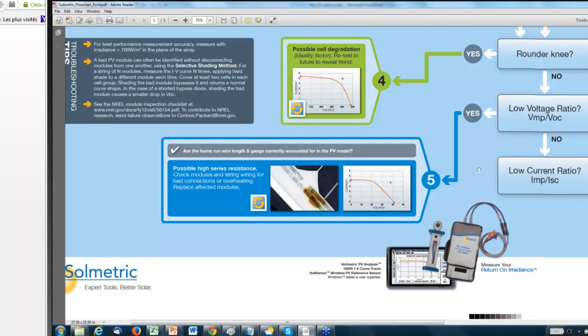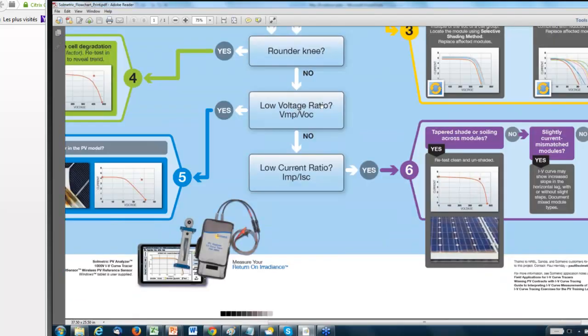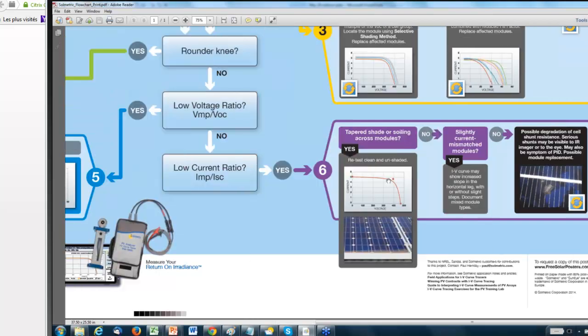If the voltage ratio is not low, you have a low fill factor, but that's not the answer, then you drop down one more box to check to see if the current ratio is low. And what we mean by that is that there's some slope, more slope than there should be, across the horizontal leg of the IV curve. And you see in that first IV curve there that it's coming across a little bit too low an angle to hit that expected max power point.